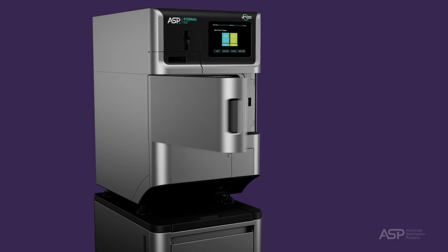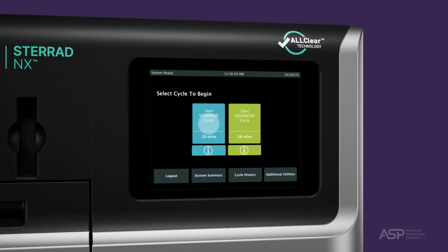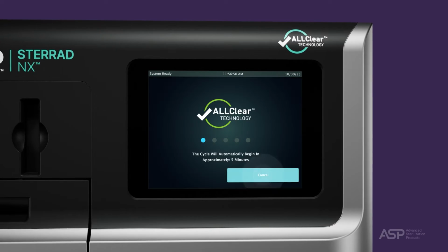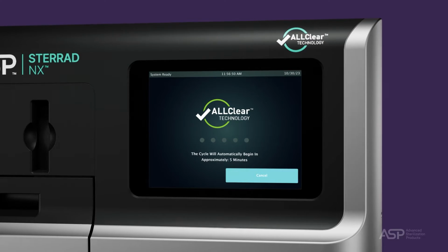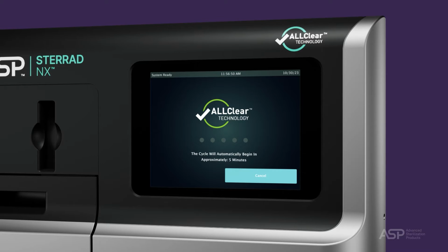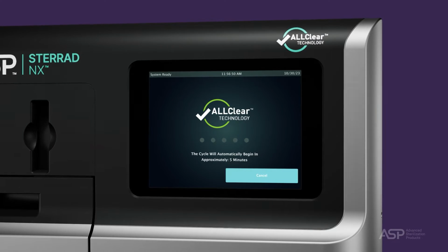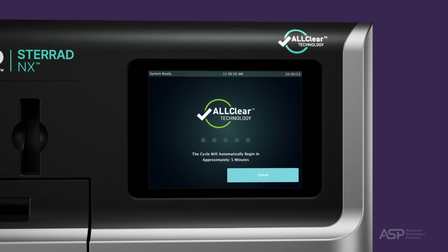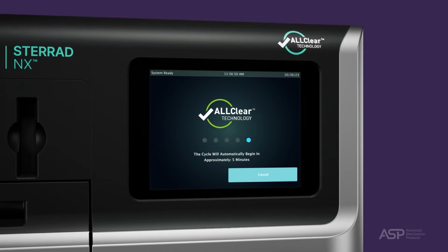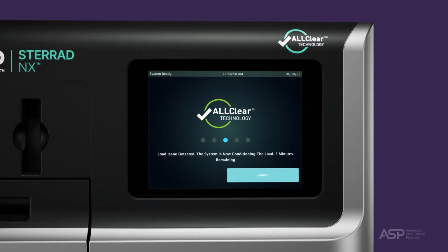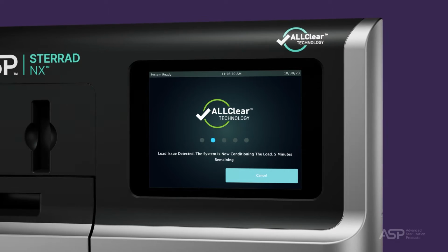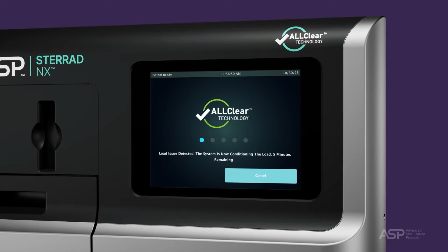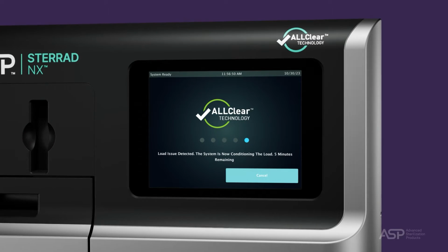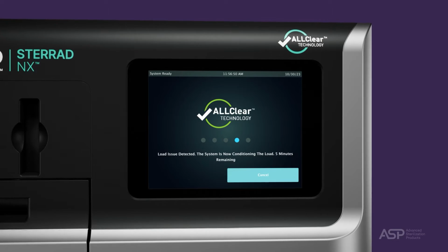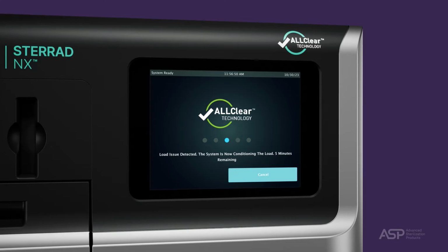Prior to beginning the cycle, the STERRAD NX sterilizer with ALLClear technology will run an automatic pre-cycle system diagnostic test and load conditioning phase. Automatic pre-cycle system diagnostics and load conditioning will be completed in 5 minutes or less. The load conditioning process minimizes the number of sterilization cycle cancellations by detecting system issues and correcting load problems prior to the hydrogen peroxide being injected. This process completes in approximately 5 minutes and occurs prior to the beginning of the selected sterilization cycle. If a load issue is detected, the sterilizer will attempt to correct it. If ALLClear technology cannot correct the issue, the selected sterilization cycle will not be started and a notification will be displayed on the screen. By utilizing the ALLClear technology, problems with a load can be detected prior to the hydrogen peroxide being injected.